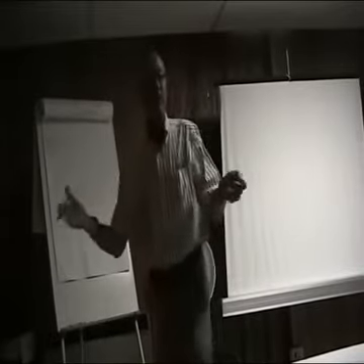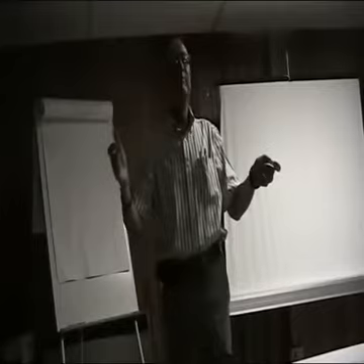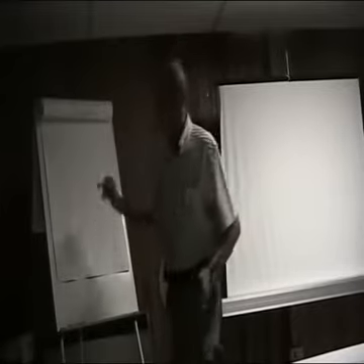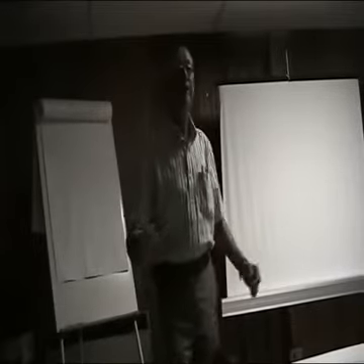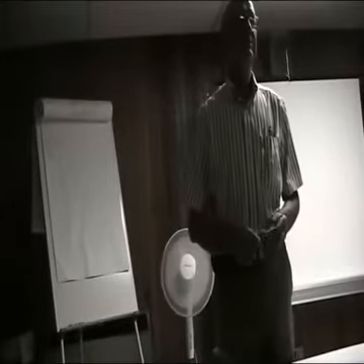Mike, you have another one? The same thing. But you'll find that everybody has different opinions. But this makes logical sense. If it's failed close, you want to force the plug down, flow tending to close, to assist you to make it close.